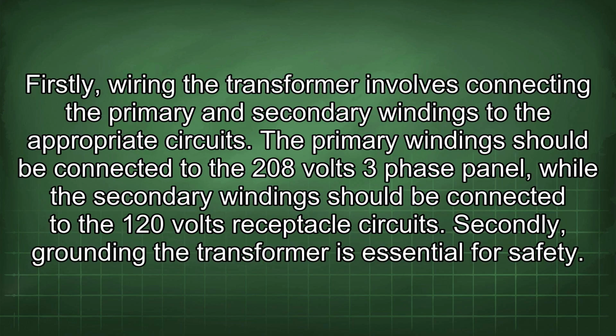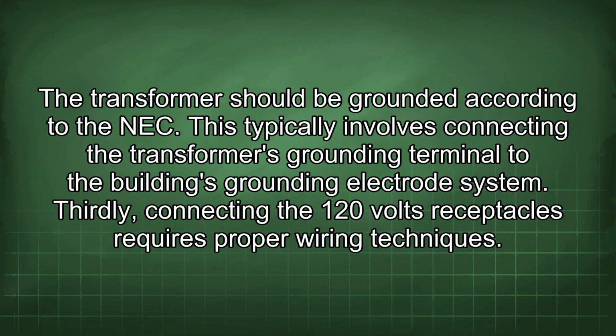Firstly, wiring the transformer involves connecting the primary and secondary windings to the appropriate circuits. The primary windings should be connected to the 208 volts three-phase panel, while the secondary windings should be connected to the 120 volt receptacle circuits. Secondly, grounding the transformer is essential for safety. The transformer should be grounded according to the NEC. This typically involves connecting the transformer's grounding terminal to the building's grounding electrode system.